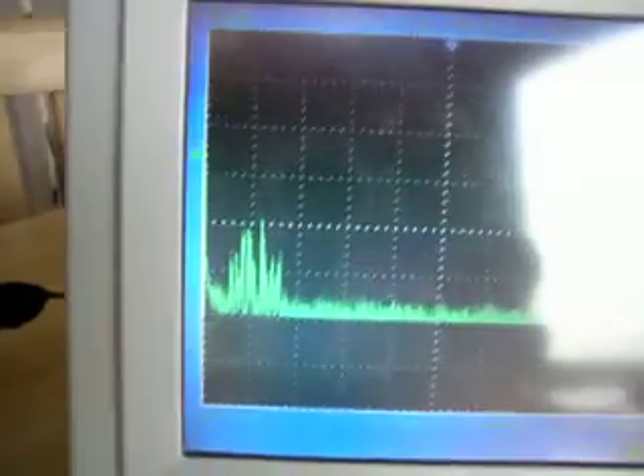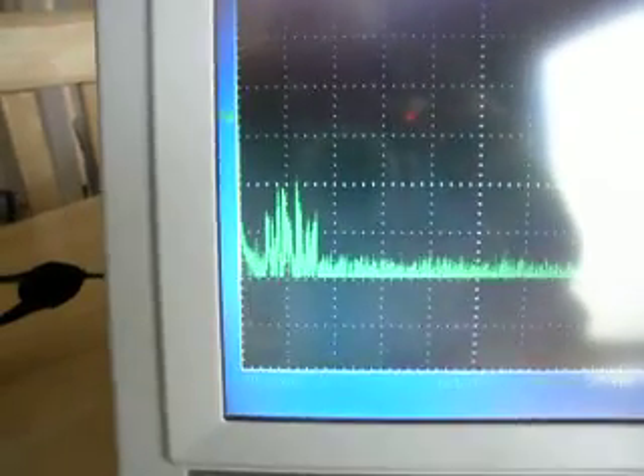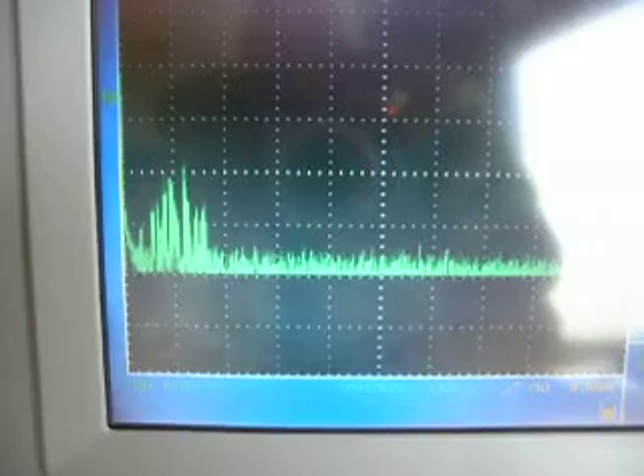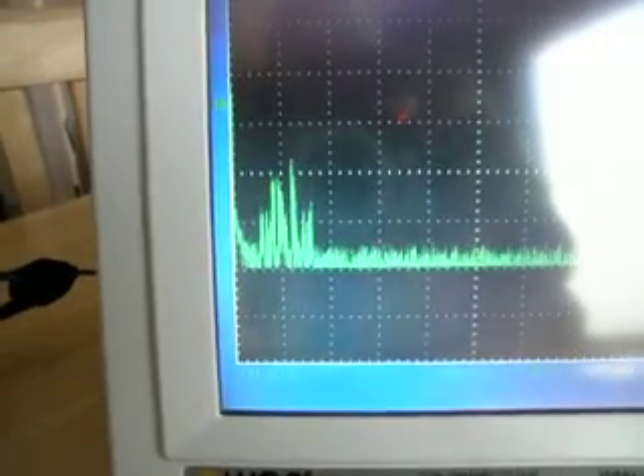So there you are. We appear to have gone right through the range of frequencies present on the grounding system. They actually go much higher, but they appear to be of a much lower level in the higher range of frequencies, above 2 megahertz.